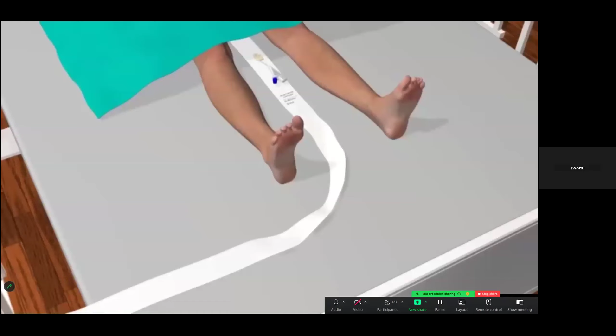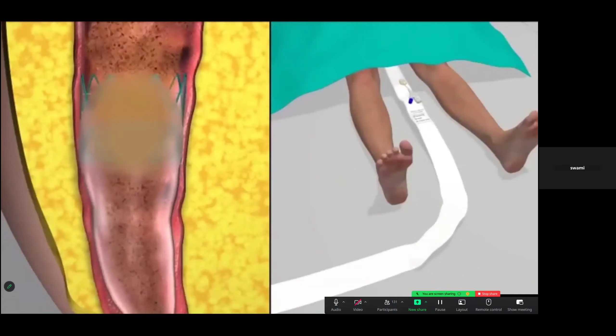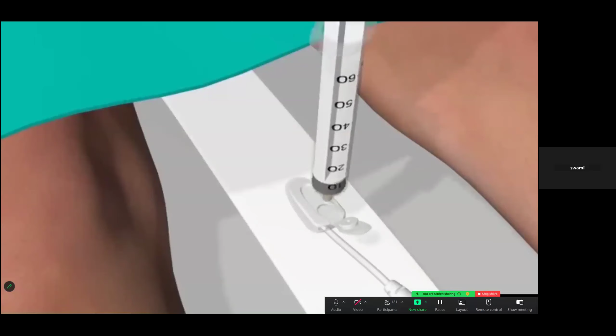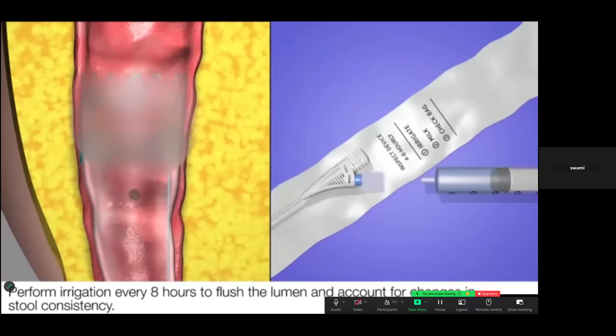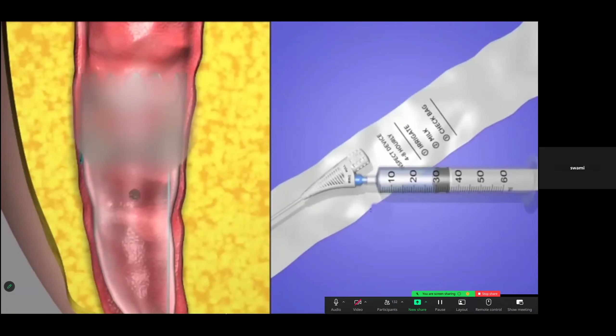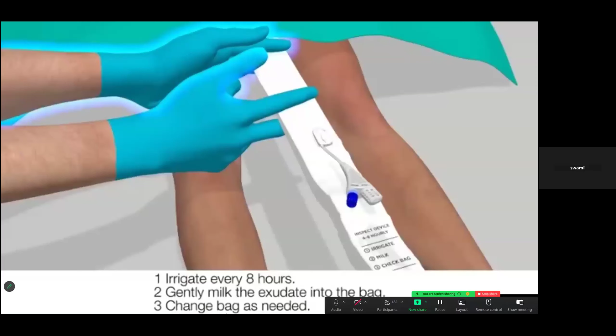The transit sheath is laid straight towards the foot of the bed. Ensure that there is an adequate amount of slack in the device. Excessive tension should never be applied to the device. The indwelling diverter conforms to the rectal wall, providing an excellent seal during use. The large lumen of the device allows varying consistency of stool to be collected. If a stool sample is required, open the sampling port cap and aspirate. Close the cap. Perform irrigation to clear the lumen and to facilitate easy transfer of fecal material. To irrigate the device, attach a Luer lock syringe filled with 20 to 30 milliliters saline solution and gradually depress the plunger. Secure the transit sheath near the patient's perineum with one hand and use two fingers of the dominant hand to drain any fecal matter into the collection bag.